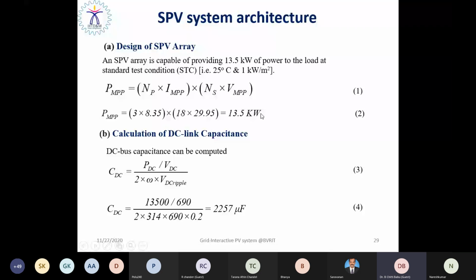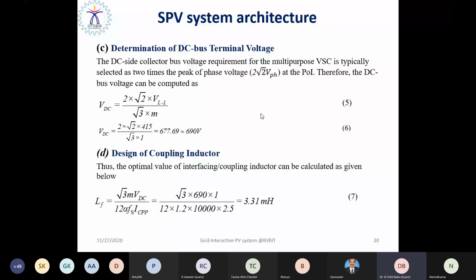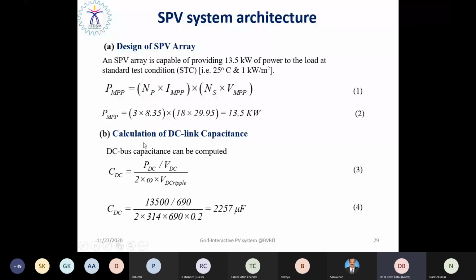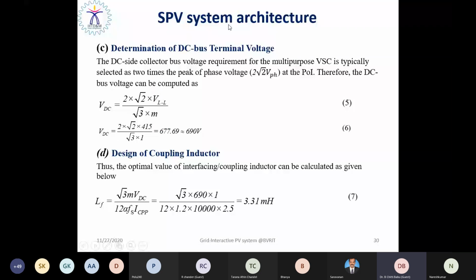Then for transferring this DC power, the DC link voltage is very essential, as the energy can be stored in the form of DC. It transfers the PV power of 13.5 kilowatts, and the boost converter boosts the voltage from 540 to 690 volts. The DC capacitor has been designed as 2257 microfarad, assuming that the DC voltage is about 690 volts. The DC bus voltage has to be designed as 690 volts so that we are able to invert 690 volt DC into 415 volt line to line, right? Because we use pulse width modulation, the effective utilization of the DC link is not good. The effective utilization would be around 78.5%, so we have to set the DC link voltage at around 690 volts.